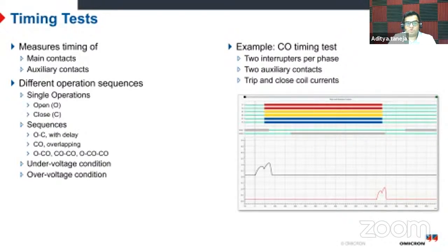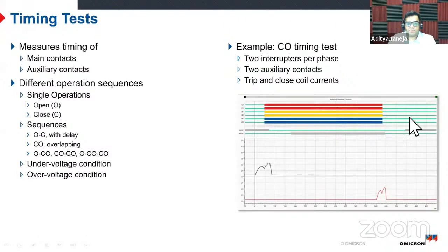or open. If it is closed, it gives a thick line. If it is open, it gives a thin line. And then this is for the main contacts. This is for auxiliary contacts. And also we record coil currents, trip coil currents here. So where we are giving the command, it comes here. This is the feedback which we get from the main contacts of the breaker.